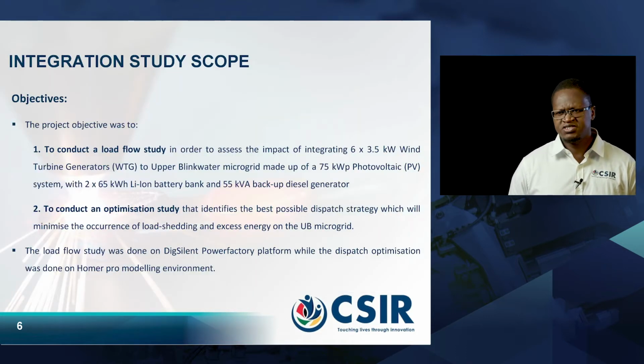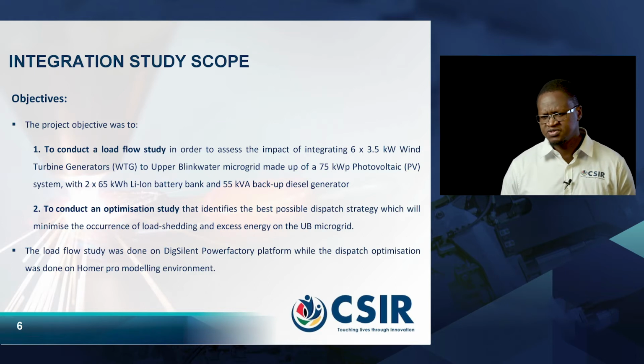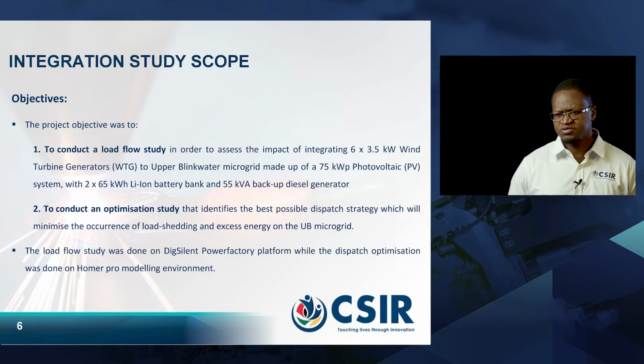In terms of the integration study scope and objectives, the project objective was to conduct a load flow study in order to assess the impact of integrating 6 by 3.5 kilowatt wind turbine generators into the Upper Blinkwater microgrid, which was already made up of a 75 kilowatt peak photovoltaic system with a 2 by 65 kilowatt lithium ion battery bank and a 55 kVA backup diesel generator.